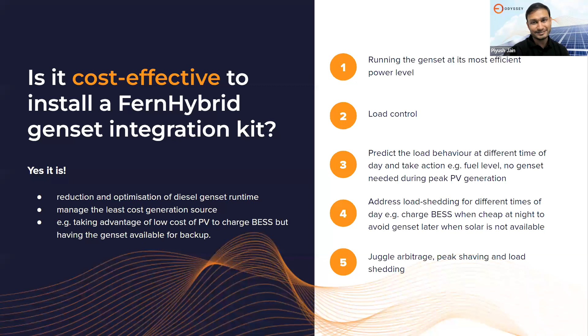Maybe one last point to make here is that there can be conflicting interests within a generator system. If you've got battery storage, a generator, and PV, you're continuously making a compromise between what you want to achieve. The generator shouldn't be running if the weather's going to be okay the next day, since the PV will pick up the load and recharge the battery, so you're fine having a very low state of charge early in the morning. But on other occasions, the weather's bad and you're expecting a grid failure, so you need to keep the state of charge of the battery much higher.